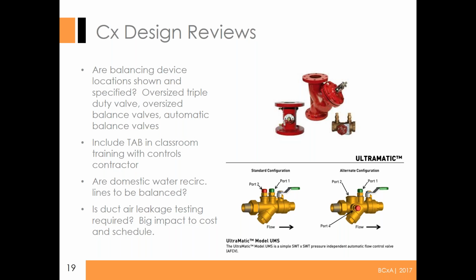So the thing to look for is whether duct air leakage testing is required. It has a huge impact on cost and schedule, and in my opinion, sometimes it's asked for when it's not needed. Check on that. Just remember, if they're doing duct air leakage testing, you really should stop by and watch them. So again, that impacts your scope.